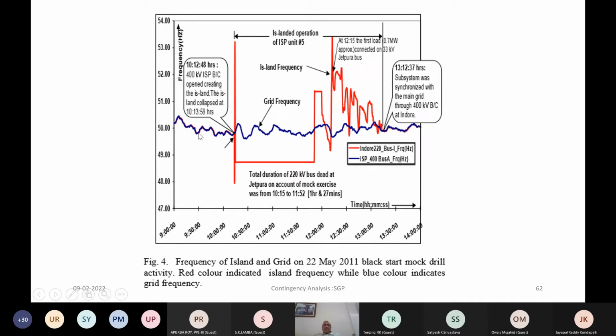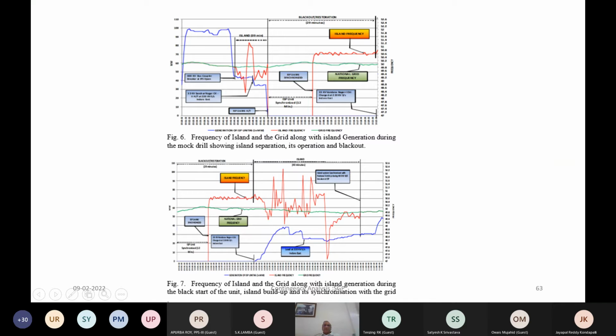Now the grid is quite stable in this blue color, but in the islanded operation of the black start area, you can see the frequency fluctuation, and then you should bring it in so that it can be synchronized at this point of time. So this island frequency was controlled, and at this point it is synchronized with the grid. So you can see various aspects of the black start procedure.